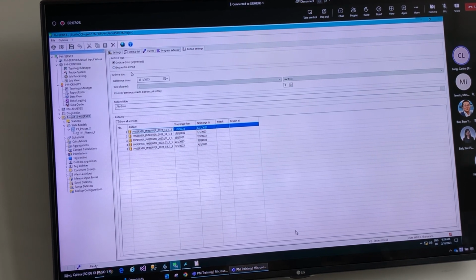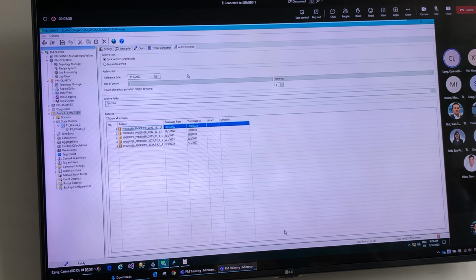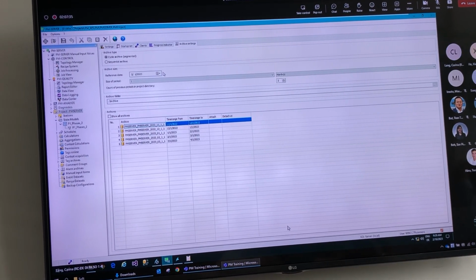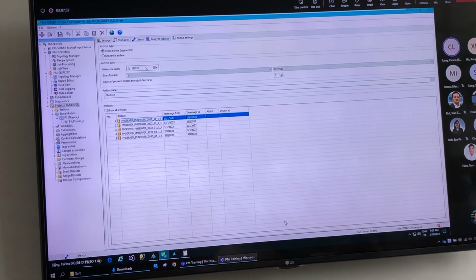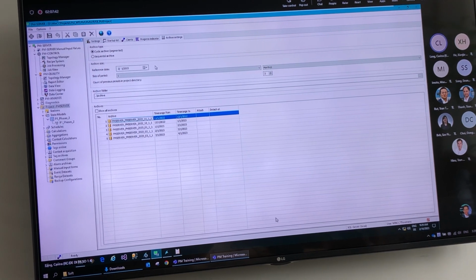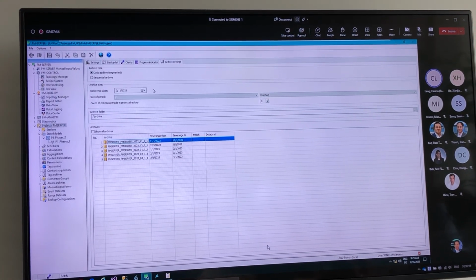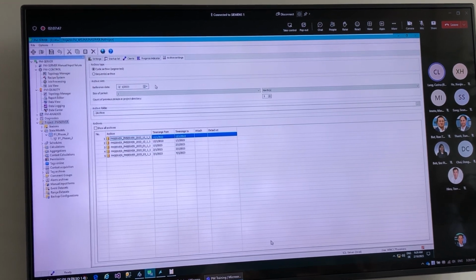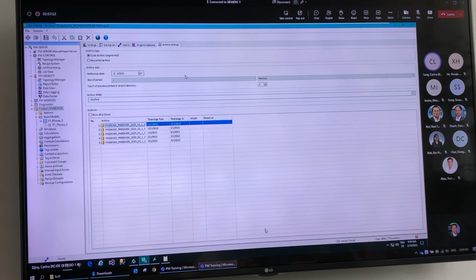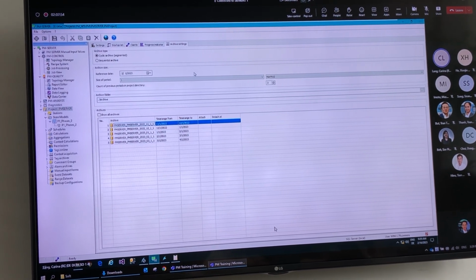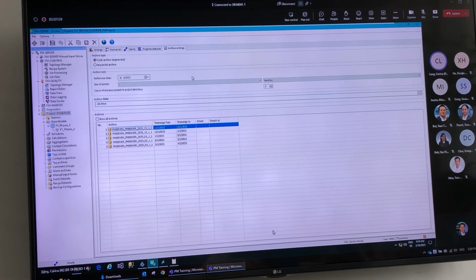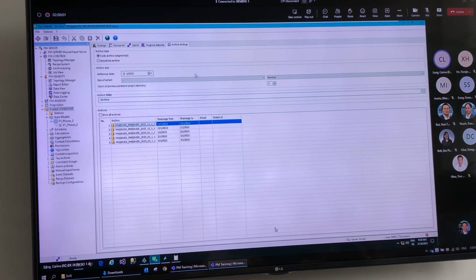Then we have to configure the archive size. So that means we have a reference date, so when we want to start with the data. In this case, it's the 1st of February this year, because the project was built up in February, because it's the current month. And then we have the size of period. So that means how much data, or the data from which time range, we want to store inside of this archive database. By default, it's always 1 month.